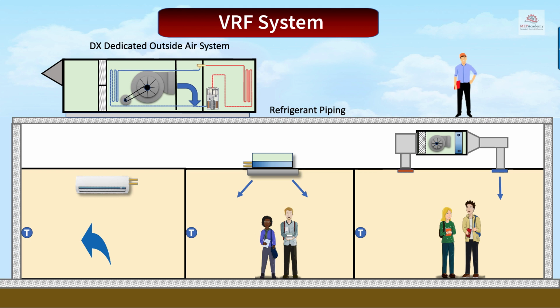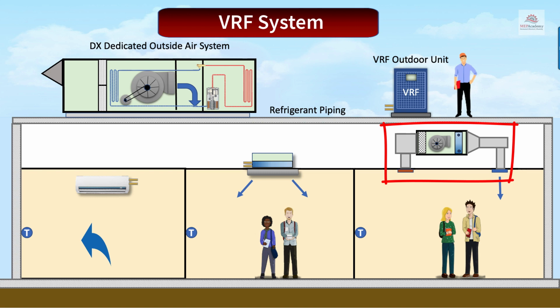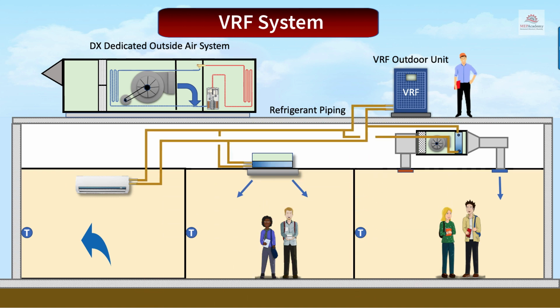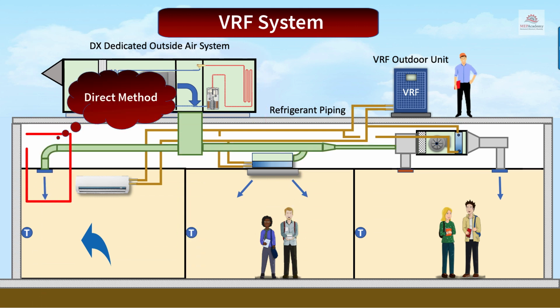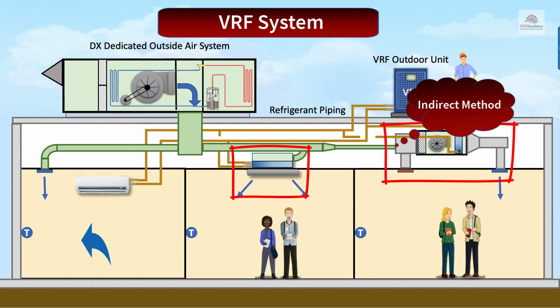DOAS units are often used with a VRF system. Here we have a VRF outdoor unit installed on the roof. We have a ducted VRF fan coil unit, a VRF ceiling cassette, and a VRF wall-mounted fan coil. The outdoor unit will be connected to the indoor VRF fan coils using refrigerant piping. We show a simple VRF heat pump system here, but this can also be used with a VRF heat recovery system. The dedicated outdoor air system is connected directly to the space for the VRF wall-mounted cassette and ducted indirectly to the VRF ceiling cassette and the VRF concealed ducted fan coil unit.